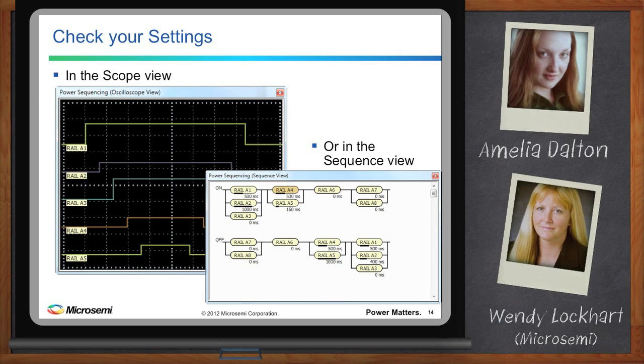You can also leave empty slots if you know you have something you may need to add later, or for system adjustments. This view also illustrates one of the power down modes, which reverses the slots of power up, so the same rails are grouped together, but can have custom delays within the slots. The other power down modes that we support are also forward and simultaneous.